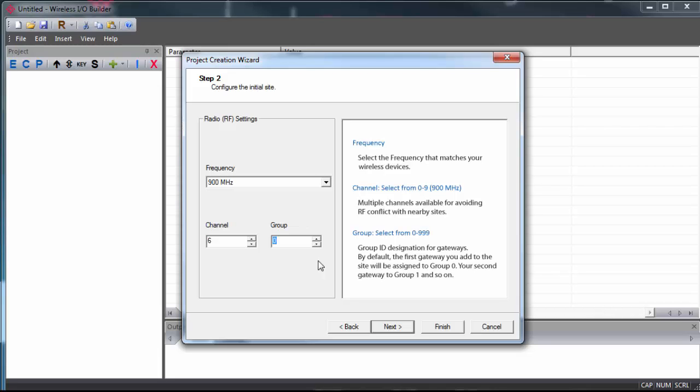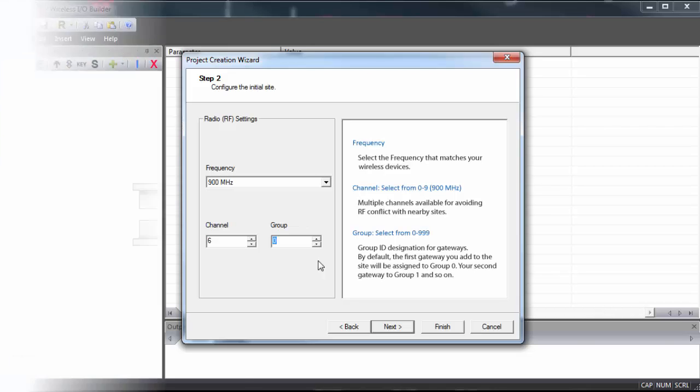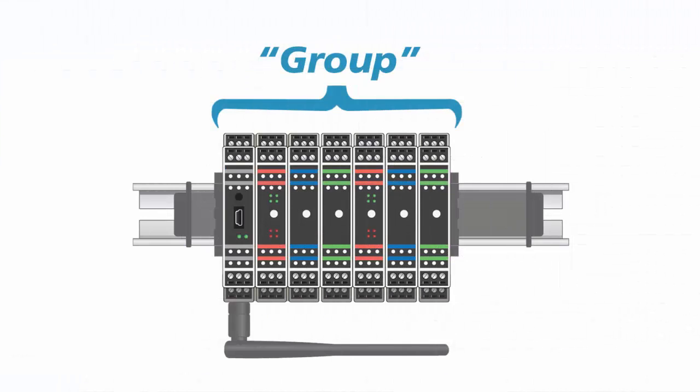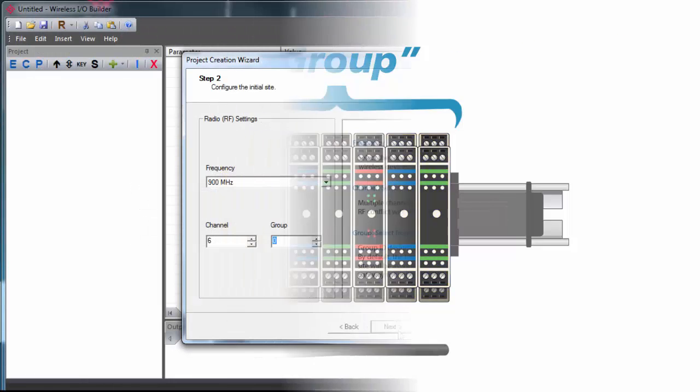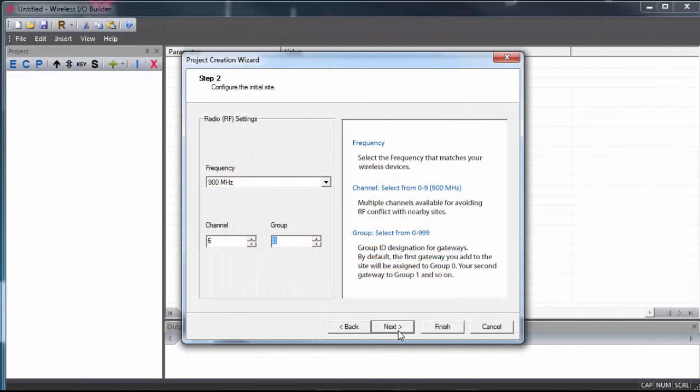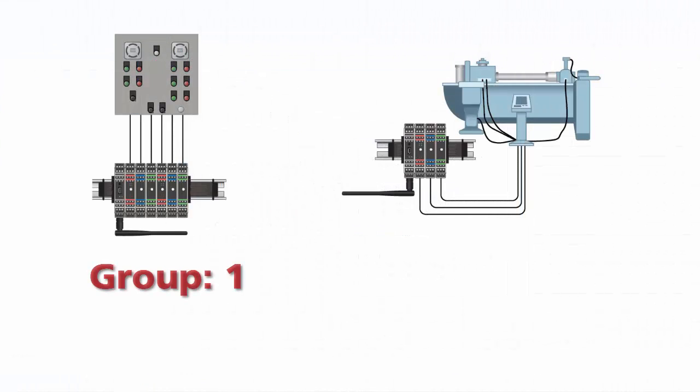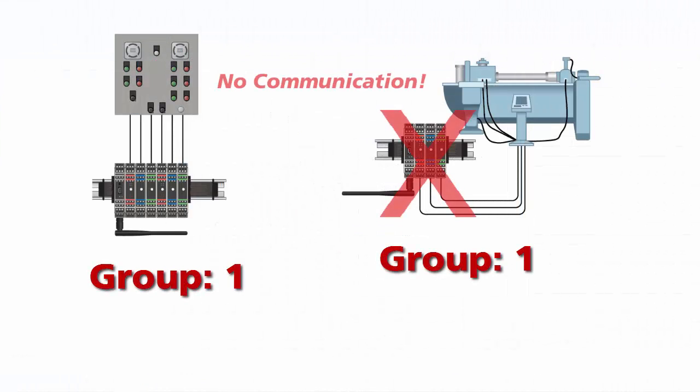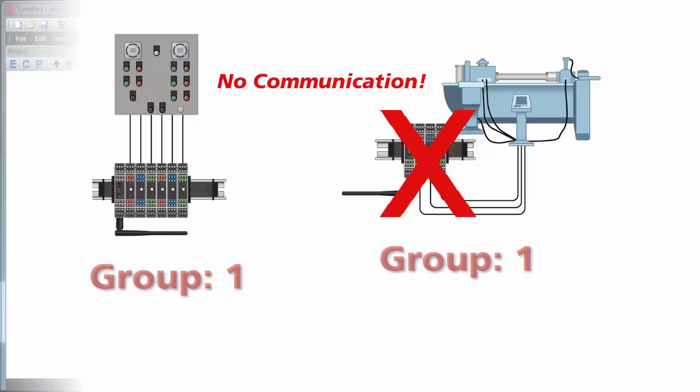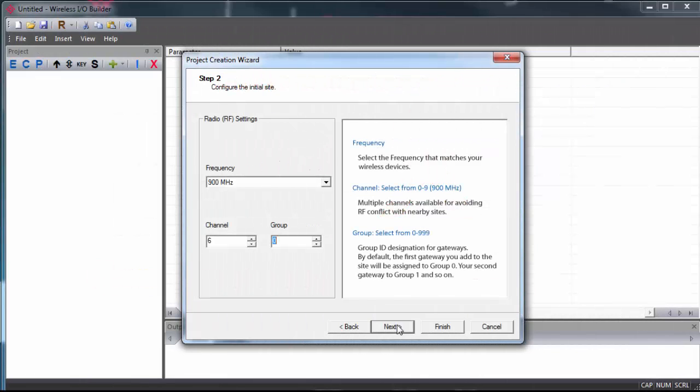Finally, we can set our group. In this instance, the term group is used to refer to an individual multipoint wireless I.O. gateway and whatever I.O. modules they are connected to. By default, the first gateway you add will be assigned group zero, and the next will be assigned group one, and so on. Just note that you can't have two gateways with the same group number on the same network.